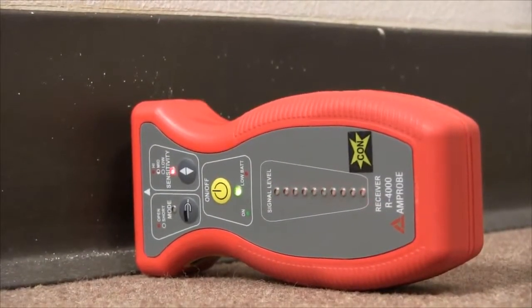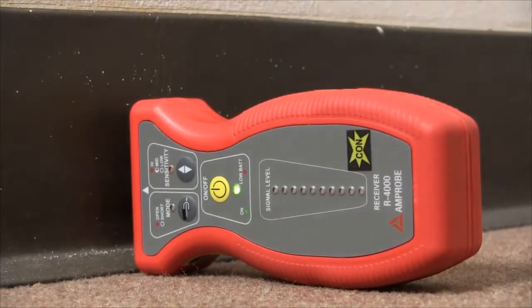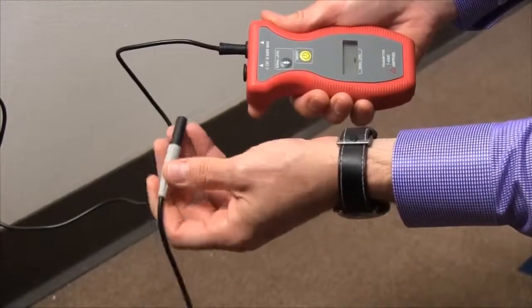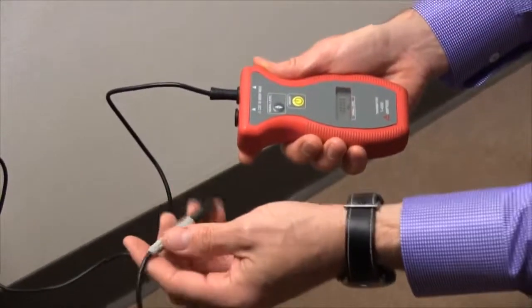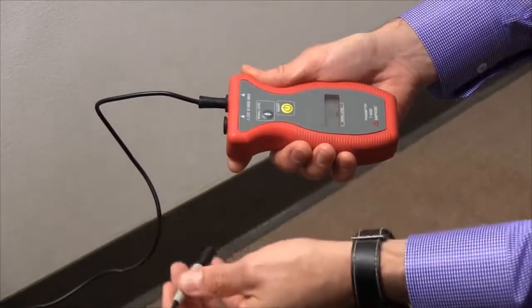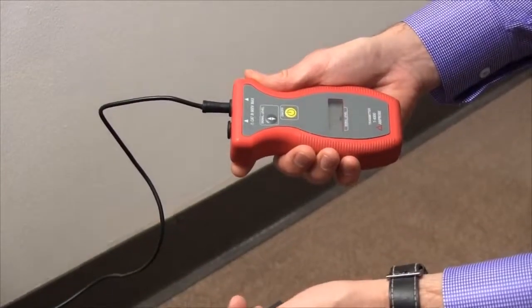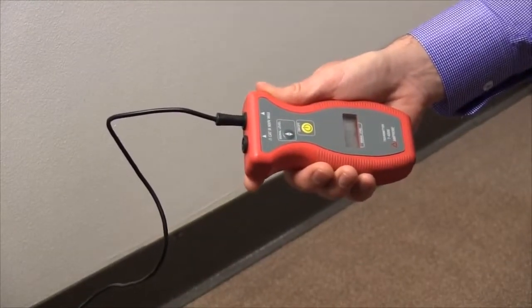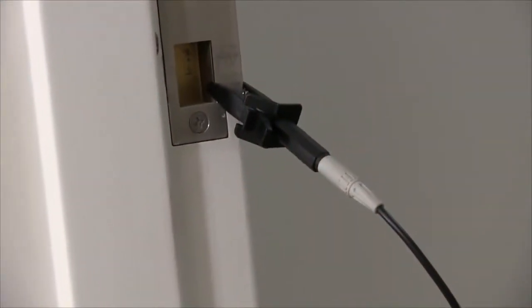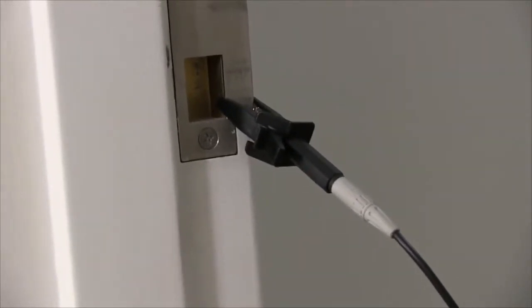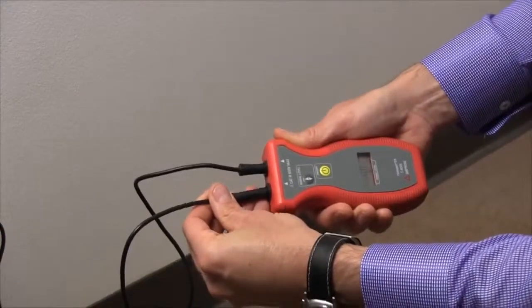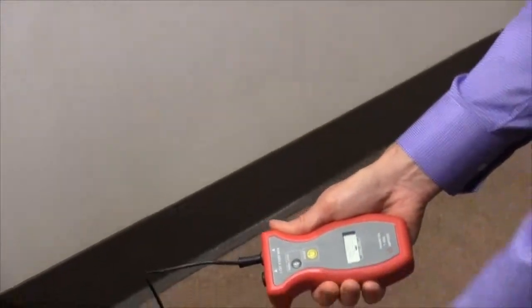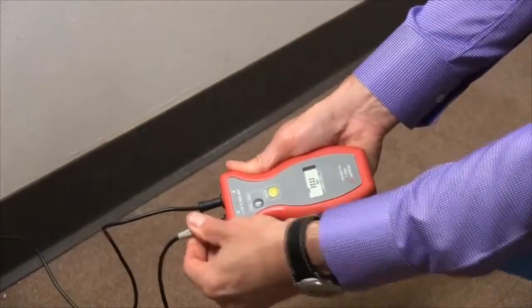Now I said that we would show what happens if you don't actually have this grounding plug plugged in. And the other end of this grounding plug is going to be, in this case, we've attached it to a metal door frame. It could also go out a window to the ground, to perhaps a screwdriver plugged into the ground. But it's important to actually have a valid grounding source, such as a standpipe, a metal standpipe, or some other metal object. You'll notice that if I plug in the other plug into the input, there's nothing. As soon as I plug the ground back into the unit, the signal returns.